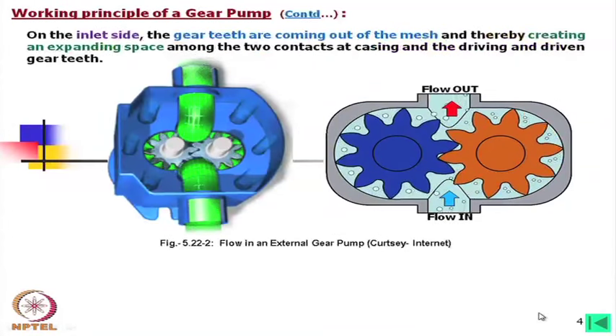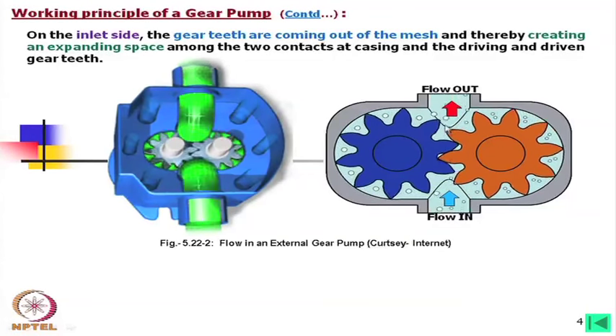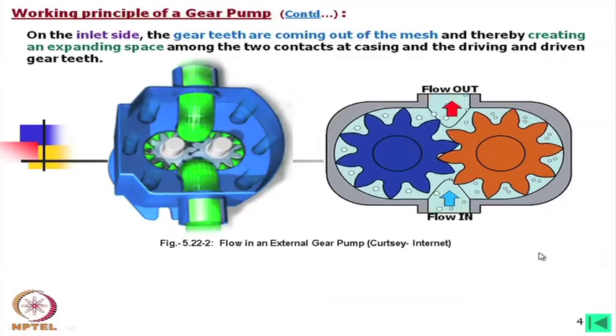On the inlet side, the gear teeth are coming out of mesh, thereby creating an expanding space among the two contacts at the casing and the driving and driven gears. If we consider the contact point that separates the high-pressure zone from the low-pressure zone, from this point to that point, when the gears are moving, this space is increasing — so there is suction. Whereas on the other side, that area is decreasing. We will derive how much this area is increasing or decreasing to find the flow rate of the gear pump.